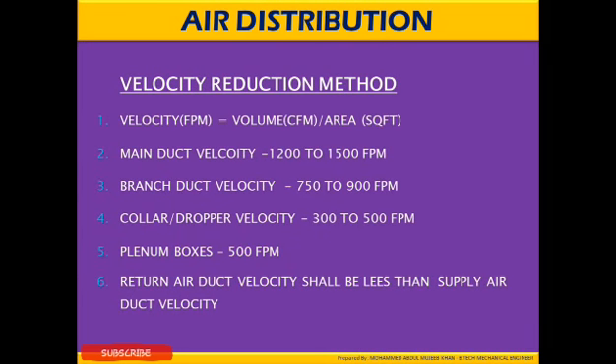Now let's look at the velocity reduction method. Velocity, which is measured in FPM, feet per minute, is equal to volume by area. Main duct velocities should be considered between 1200 to 1500 FPM. Branch duct velocity should be considered from 750 FPM to 900 FPM. Collars, drops velocity should be considered between 300 to 500 FPM. Plenum boxes should be considered 500 FPM. Return air duct velocity shall be less than the supply air duct velocity.